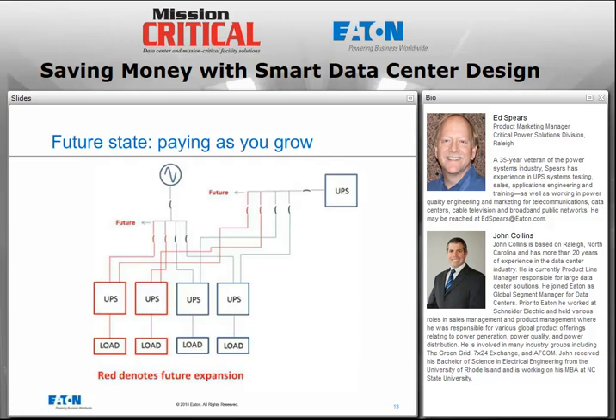So in a traditional catcher system, the UPS which suffers the fault would immediately see an overload. It would go into current limit, and it would transfer to bypass on overload. But if that bypass was fed by yet another upstream UPS, in this case the catcher, well, that's another inverter there with a limited capacity for current, and it may not be able to clear the fault either, so that UPS becomes overloaded, transfers to bypass, and the utility finally clears the fault. That's a lot of things that need to happen in series.